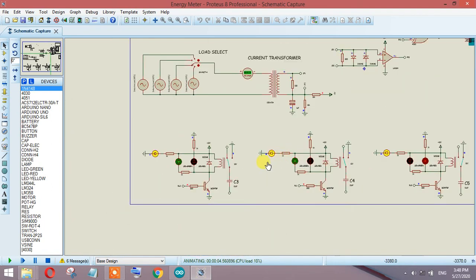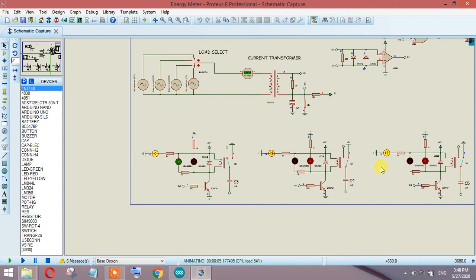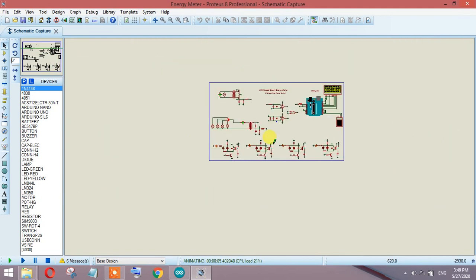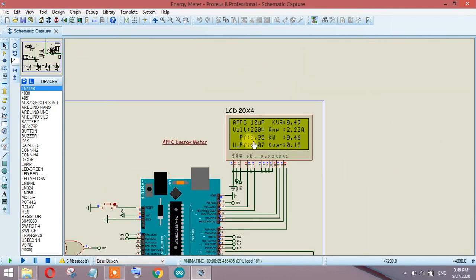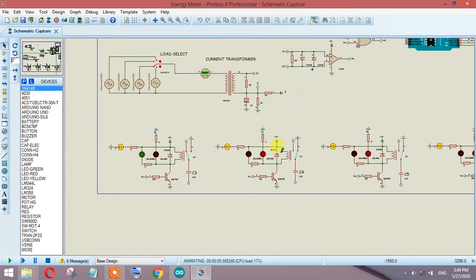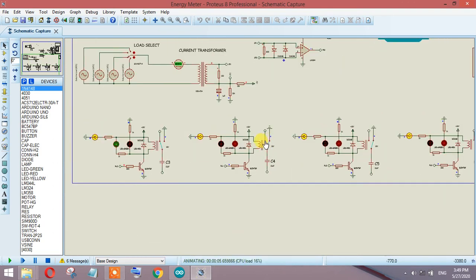To demonstrate this, if I just reverse it you will see this capacitor will be subtracted from the system or removed. The system will detect we are moving, so this thing turns off. As I move it, you can see the system will detect the power factor which will jump to 0.87, and this will be taken in line to make sure we have unity power factor.